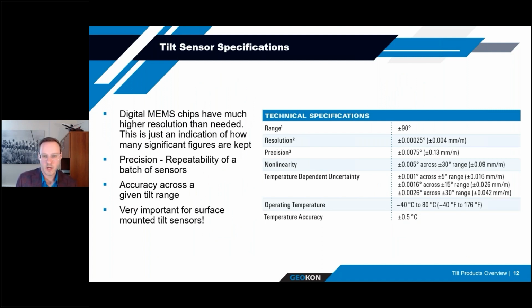So I thought I would take some time to go through a typical tilt product specification sheet. So this is for one of Geokon's tilt products here. So the first spec item is range, and this essentially just is a description of the appropriate range that would give output from the sensor. So this is different from the calibration range, of course, but if the sensor is within plus or minus 90 degrees, you will be able to get a reading.